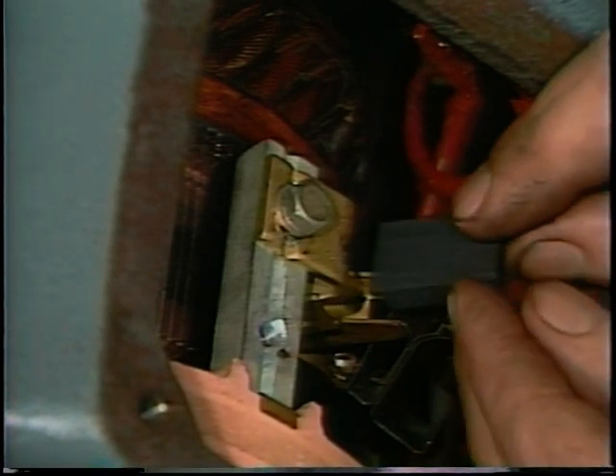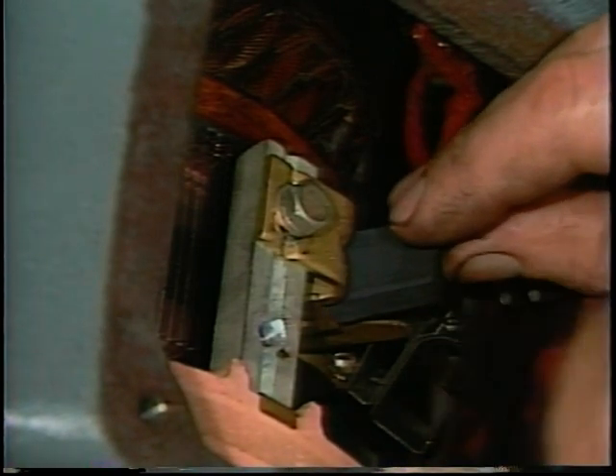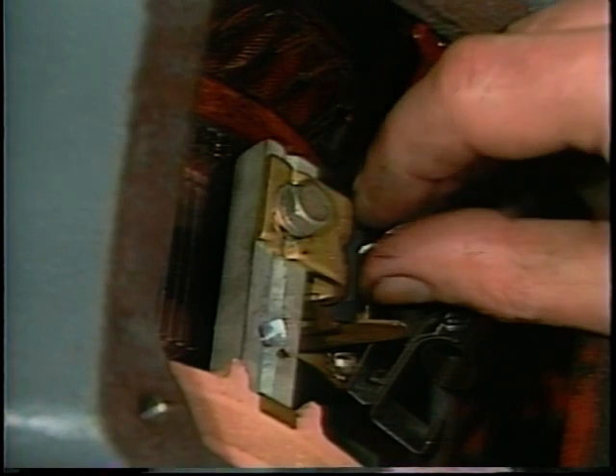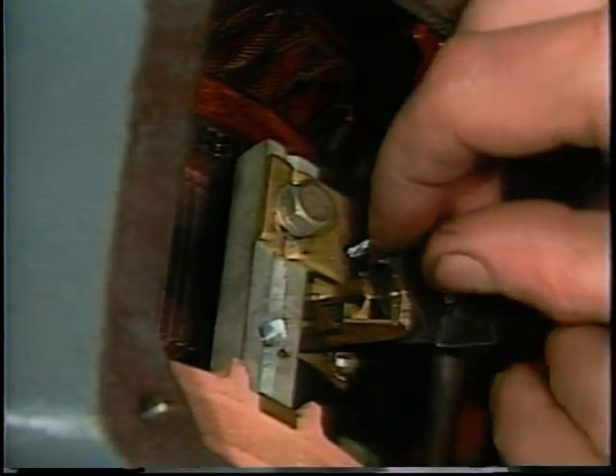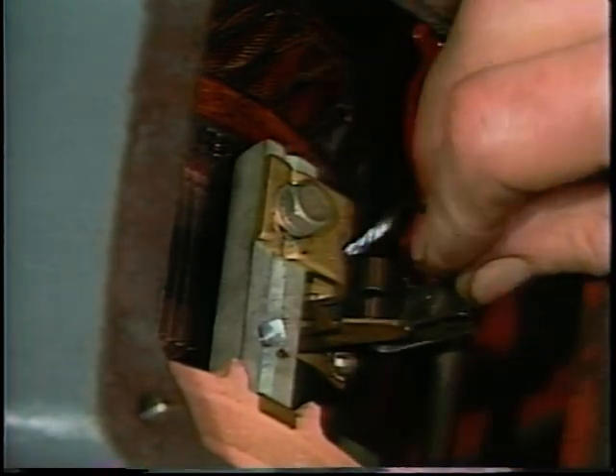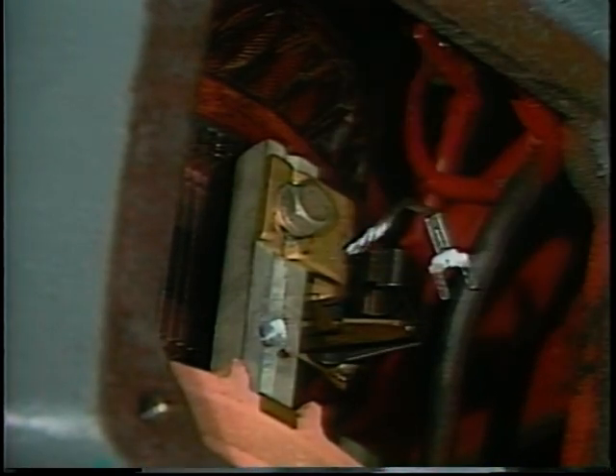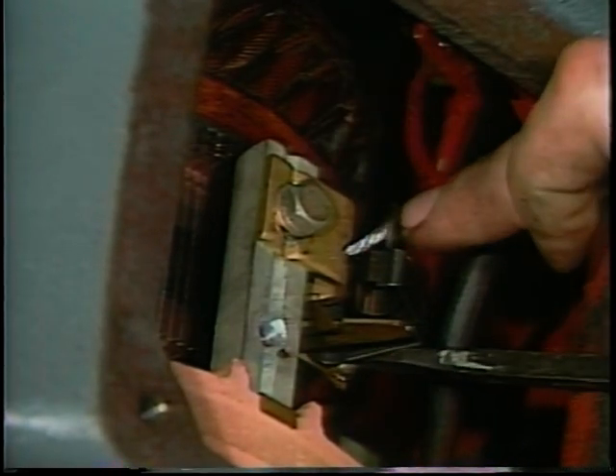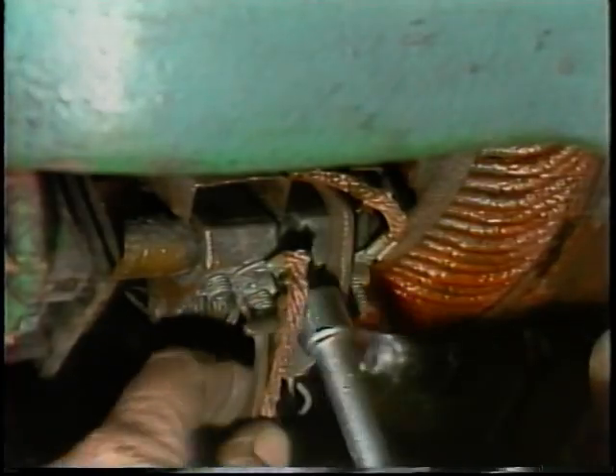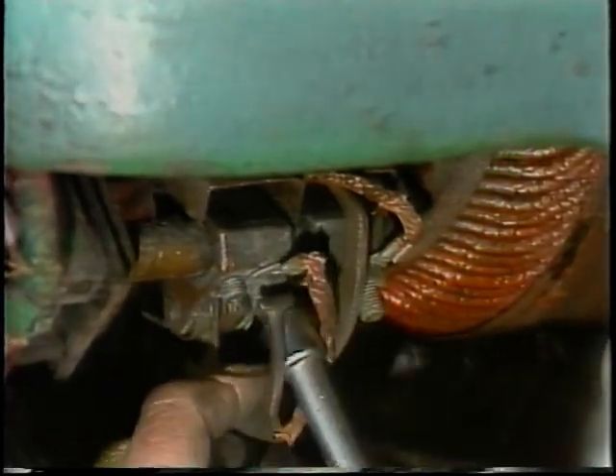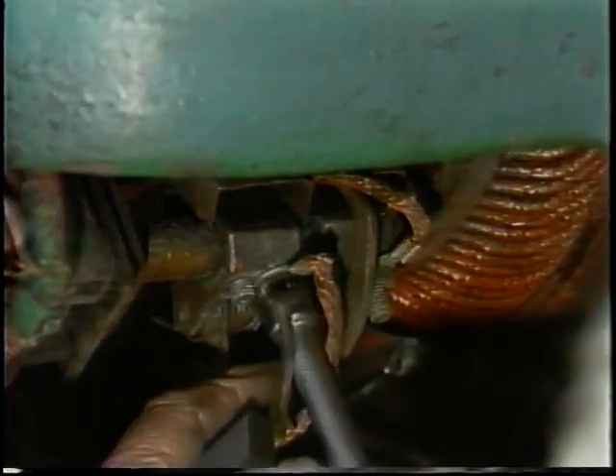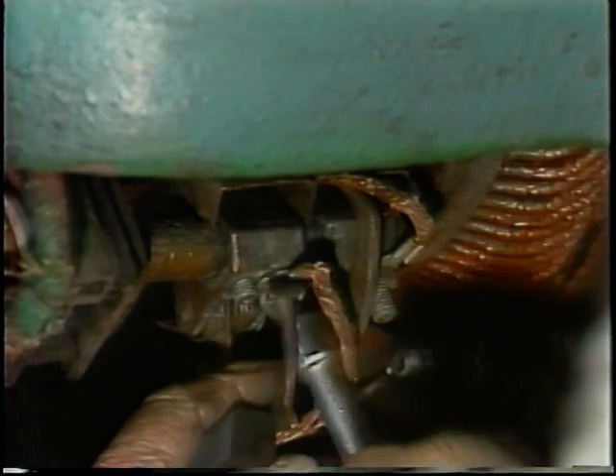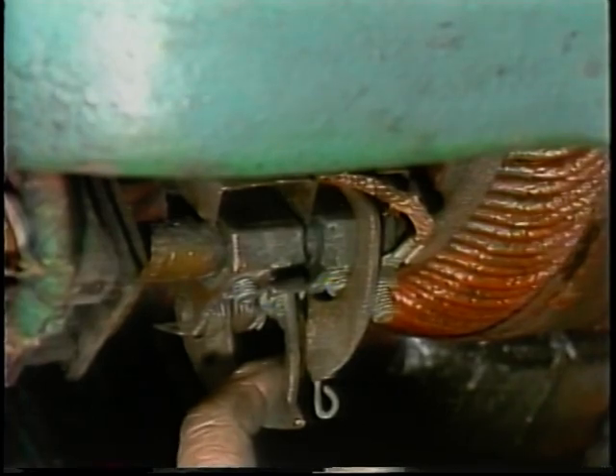Be careful not to chip or break the brushes. They are deliberately made of a relatively soft carbon, so they will wear before the copper commutator bars do. As a result, brushes are rather fragile and must be handled carefully. Now, if one or more brush is down to half its original length, worn crooked, chipped, or broken, it is a good idea to replace the complete set.